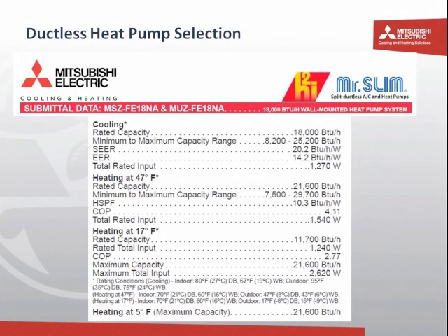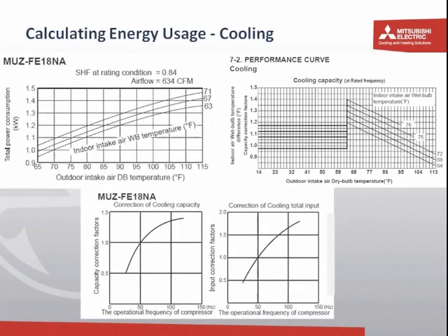Now we want to take those to your project and its specific conditions. And that's what the charts on this page do. This happens to be on the cooling side. And what it enables us to do is take a look at the design conditions that your system is going to be operating at and put in effect a series of adjustments to that nominal wattage input to determine what the actual wattage input is, both for a worst case scenario, the hottest day of the year, maybe a best case scenario, which would be the coolest temperature that you feel like air conditioning is going to be needed at all, and then interpolate a couple of points in between.